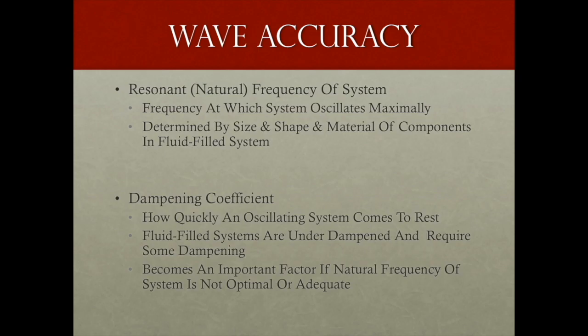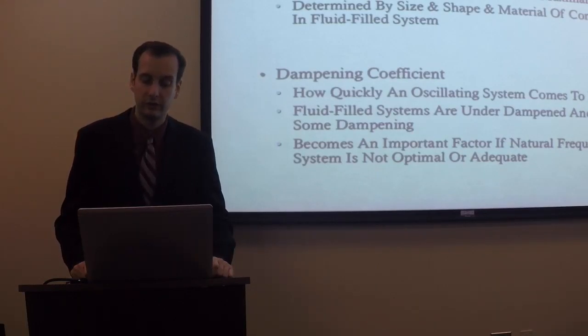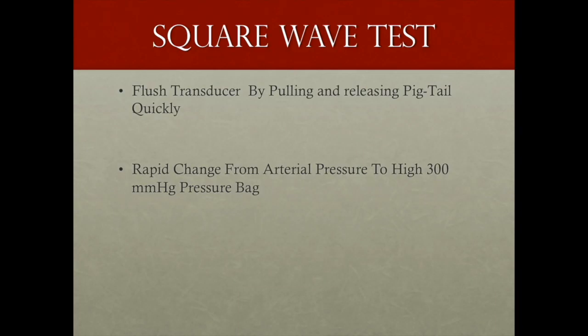All fluid-filled systems are inherently underdamped. Damping becomes an important factor if the natural frequency of the system is not optimal or adequate. The way to test your resonant frequency and your damping coefficient is to perform the square wave test. This is carried out by flushing the transducer, by pulling on the pigtail and then releasing quickly.